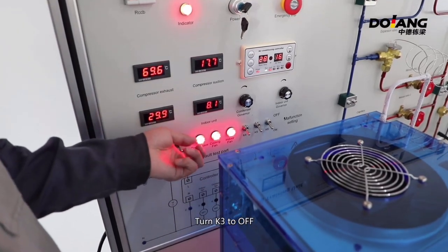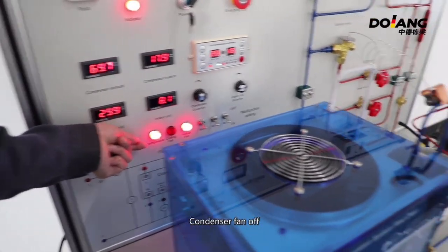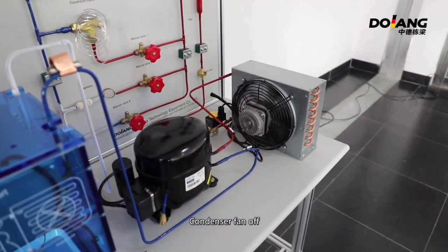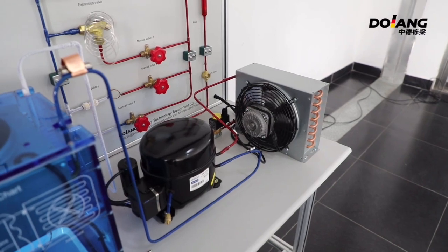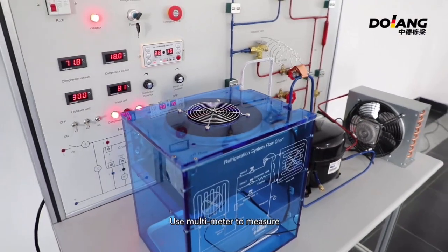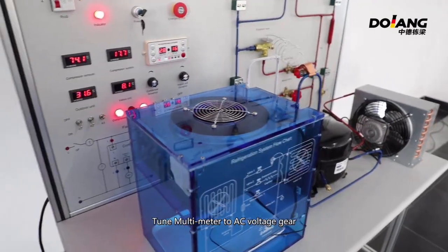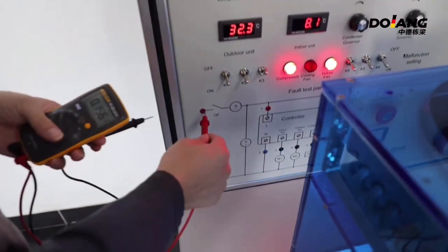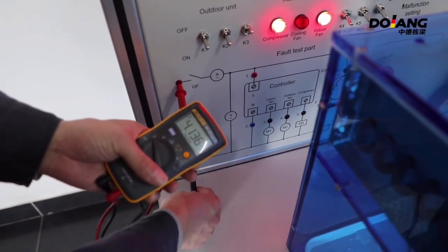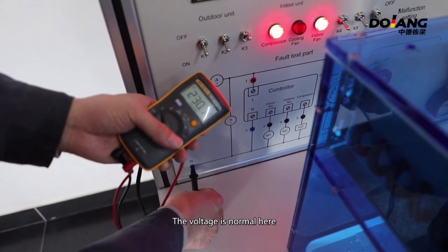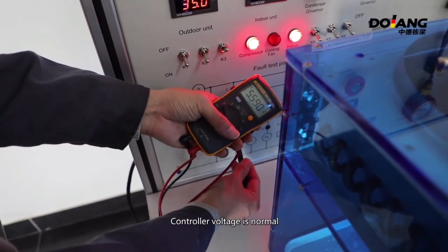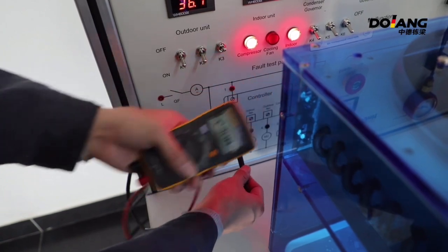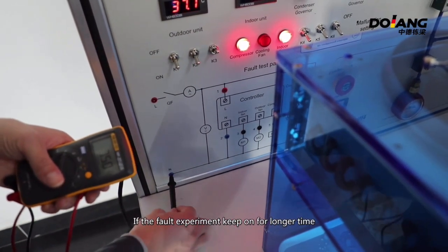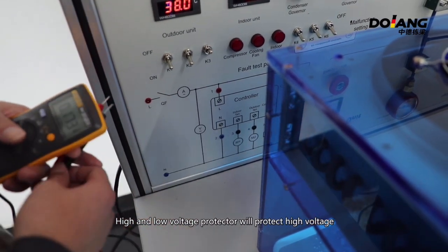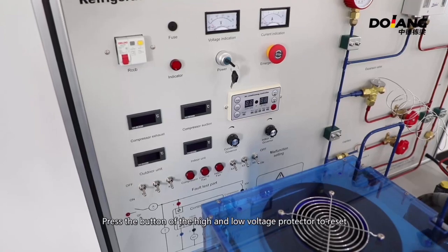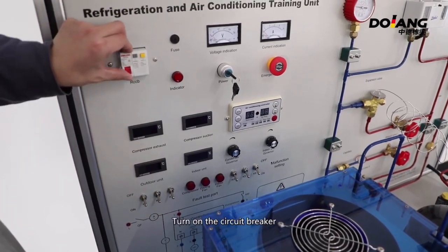Now do the third fault experiment. Turn K3 to off. Condenser fan off. Use multimeter to measure. Turn multimeter to AC voltage gear. The voltage is normal here. Controller voltage is normal. If the fault experiment keeps on for a longer time, the high and low pressure protector will protect against high pressure. Press the button of the high and low pressure protector to reset.